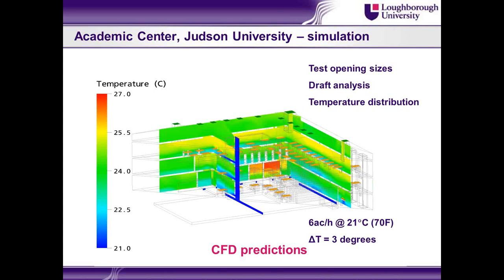Generally, when the outside air temperature was at 70 degrees F, we were able to drive naturally 6 air changes per hour, which is quite typical for a natural ventilation strategy, and to generate a delta T, an inside-outside temperature difference of 3 degrees, which is, again, what we try to achieve in naturally ventilated buildings. So we were quite satisfied that the buoyancy-driven natural ventilation mode was working in this case. It is likely to work.